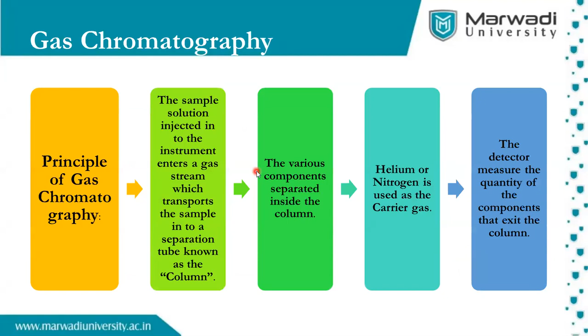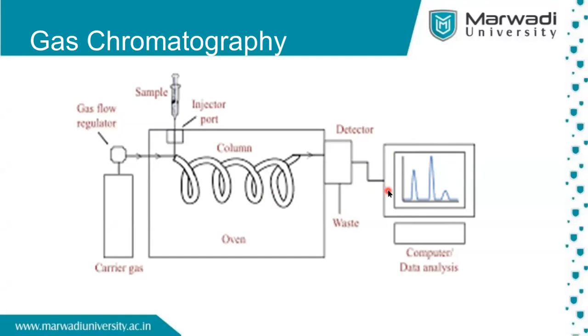Normally there are two types of column: packed column and capillary column. Capillary column is highly sensitive. Whenever the retention times are very close, when the boiling point or volatility is very close, you have to use the capillary column, and you will get fine retention times for the different components. You will have separate peaks, even though the volatility of the two or three components is very close. Then it will go to the detector, which is connected to your system PC, and you will see the different peaks on the PC, right?